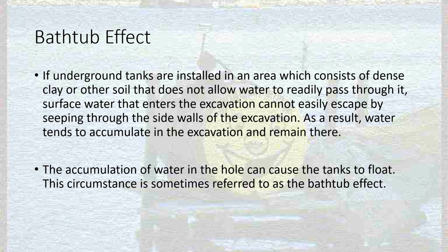And then that can create an effect on the tanks where you need to keep those tanks either A, strapped down, or B, full of some amount of fuel so that they won't float. That's one of the bad effects of the bathtub effect, is it can cause your tanks to actually pop out of the ground.